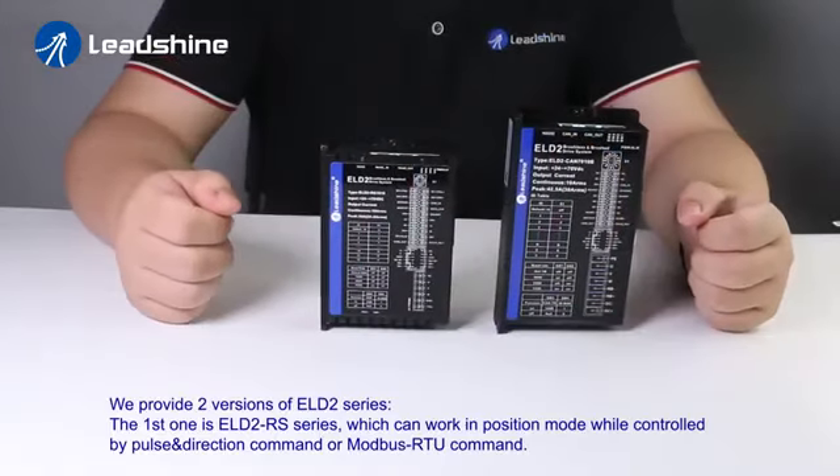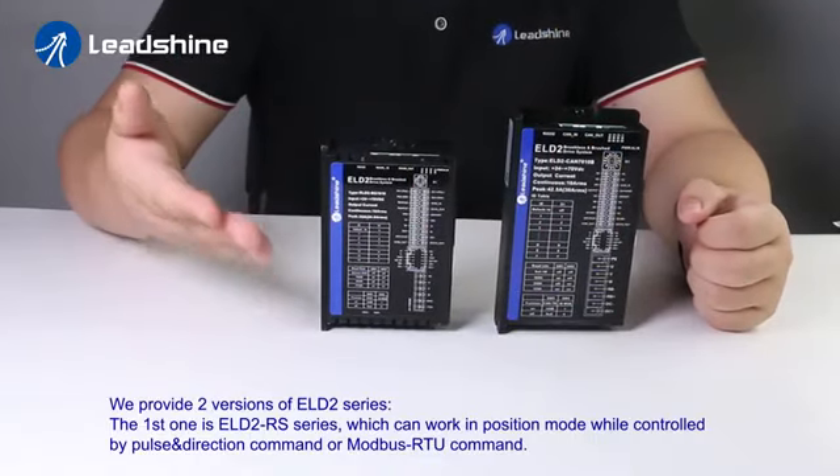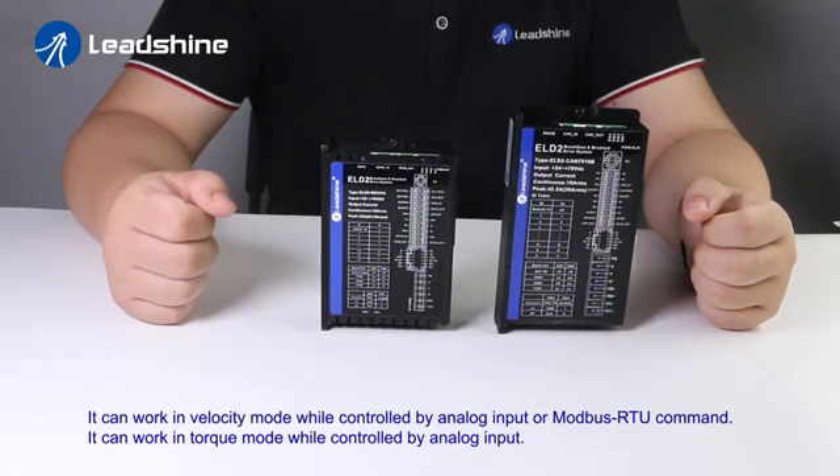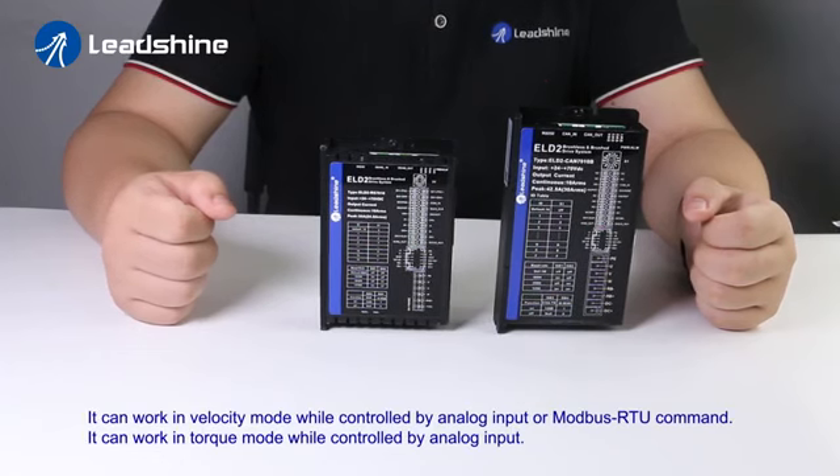We provide two versions of the ELD2 series. The first one is the ELD2 RS series, which can work in position mode while controlled by pulse and direction command or Modbus RTU command. It can also work in velocity mode while controlled by analog input or Modbus RTU command.